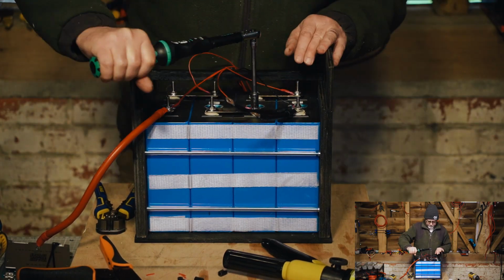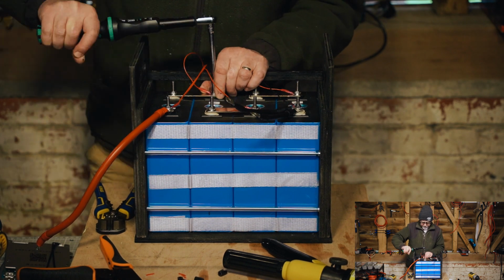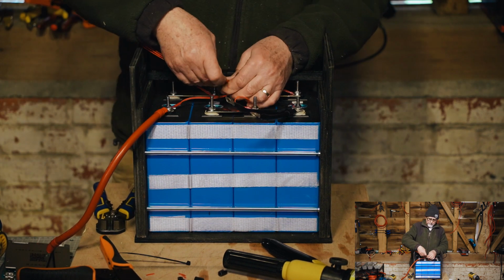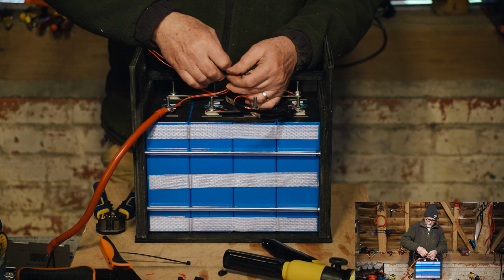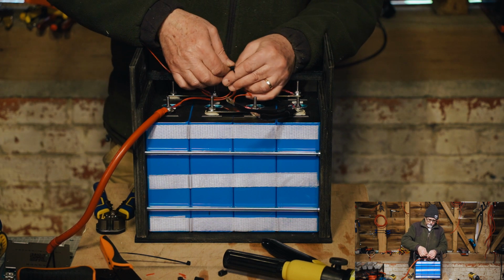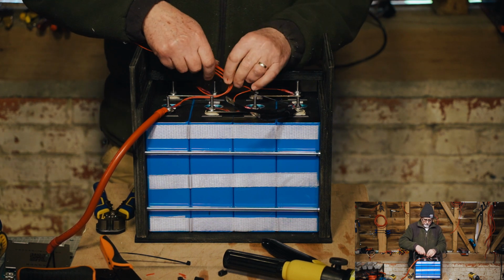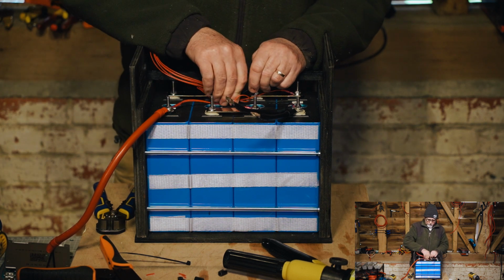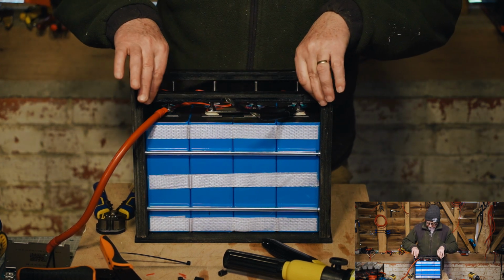And then go through and torque each one individually. Often we'll go back over them and double check, because it's easy to miss them, and you don't really want a terminal that's completely loose and hasn't been torqued down properly, because that'll be a point that generates heat, and it can be quite a big safety issue.